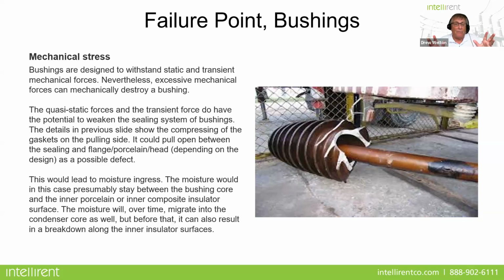You're not going to get imminent failure, but it's going to weaken it to the point where eventually it could be a potential hazard. So your forces and transient forces do have the potential to weaken not the bushing, it's just the bushing itself, but the sealing system of the bushing. So in this particular slide right here, we see, of course, a pretty intense mechanical failure. But even the slightest cracks in a bushing can lead to moisture ingress.